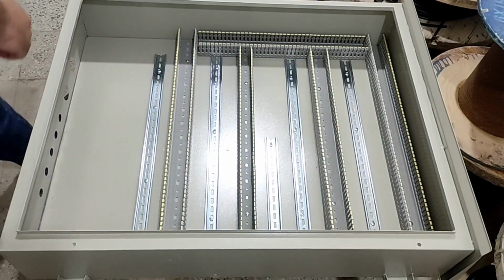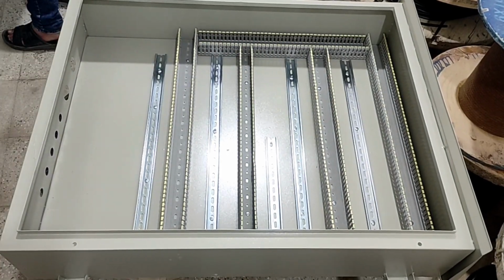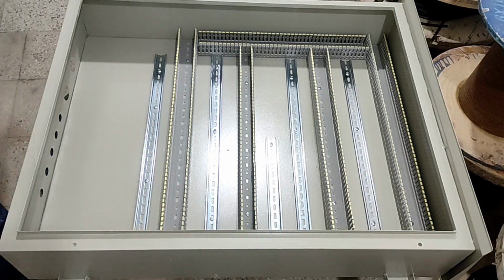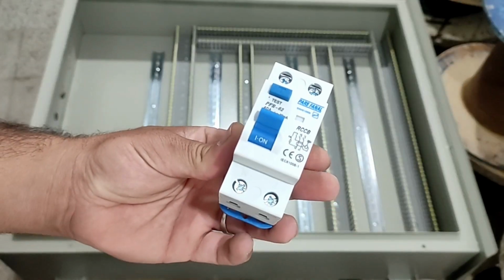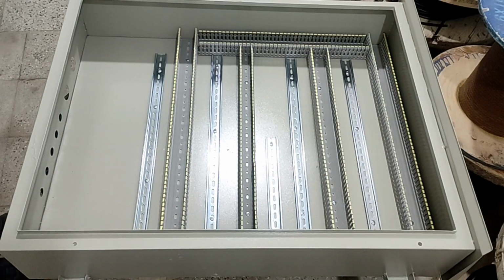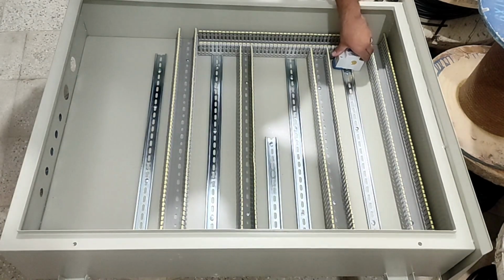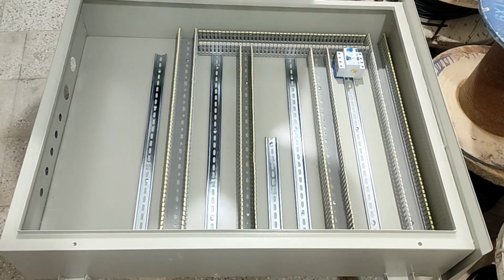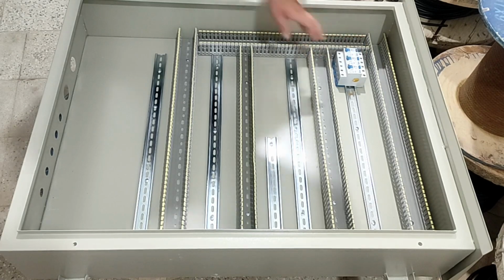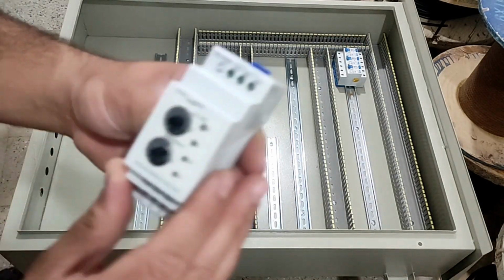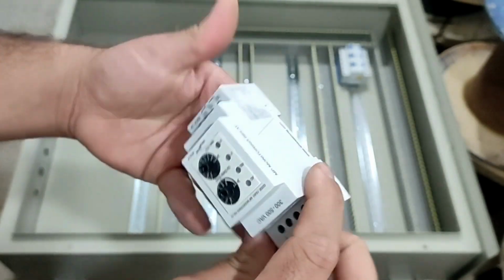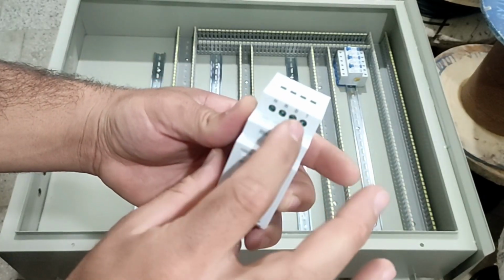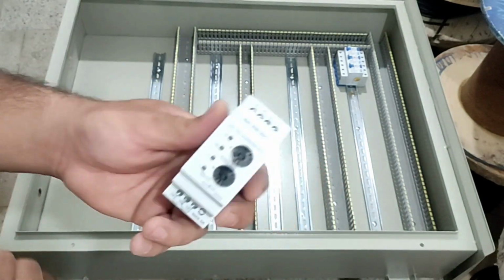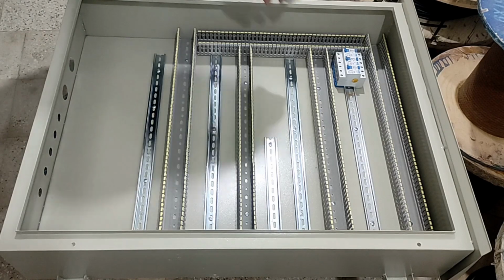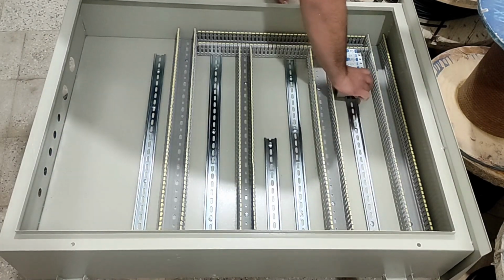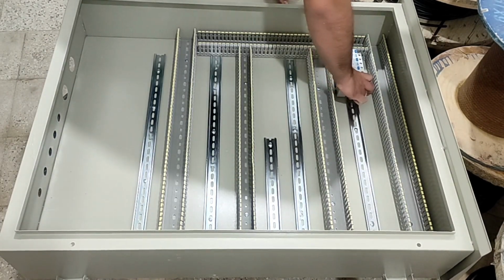The installation of rails and ducts is finished. At this stage, we will install the electrical panel equipment. This electrical panel includes 6 single-phase RCCB switches in the upper row, which we will install. Along with the 3 RCCB switches that we install, we also install a 3-phase monitoring relay to control the output phases from the RCCB switches. By installing the device, if one of the switches is disconnected, the relay is activated and sends a warning message.